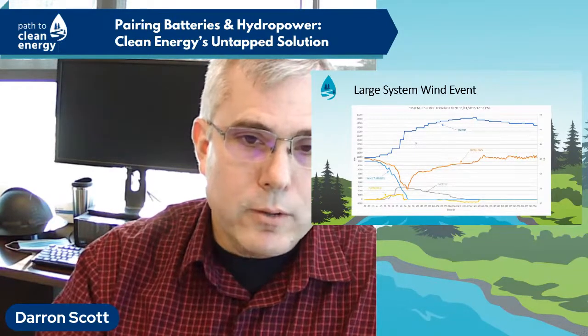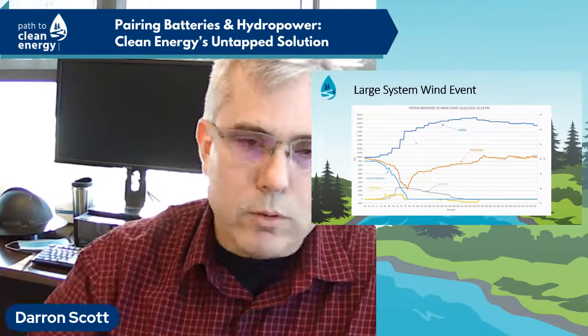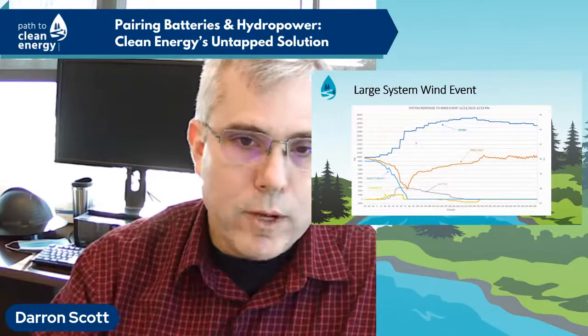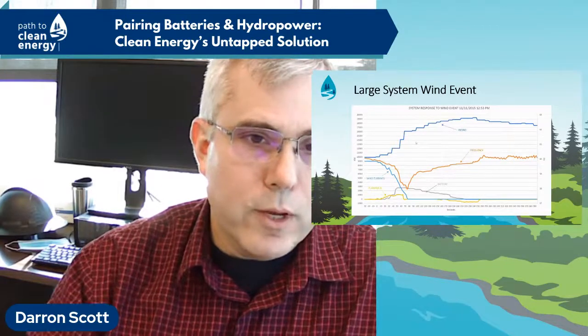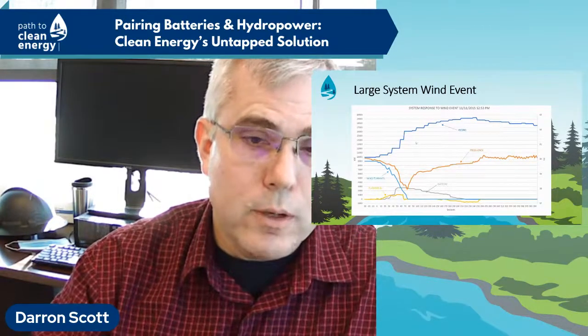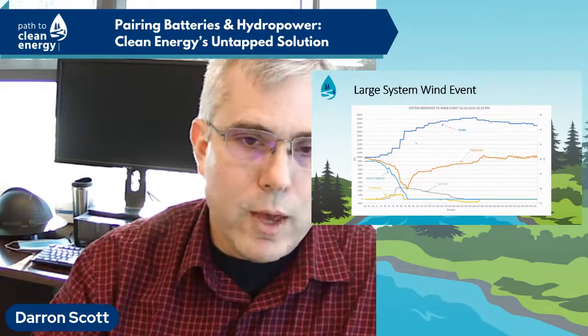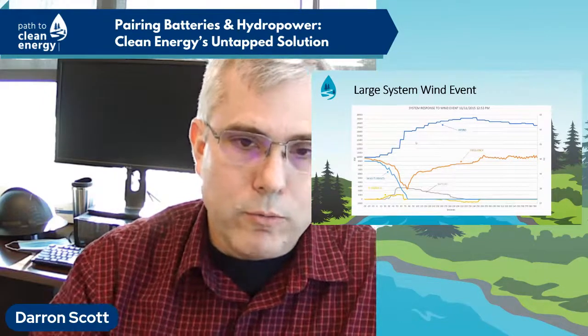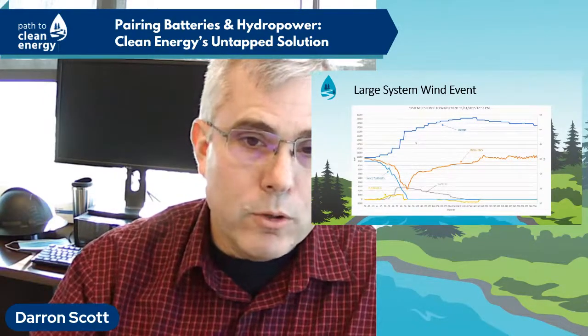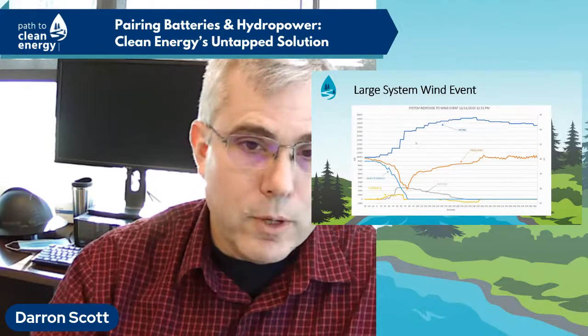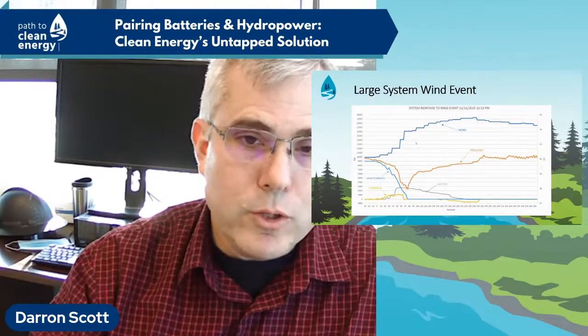That's why they're not 3 megawatts for an hour or two of energy storage. We've got them tuned down to 3 megawatts for 15 minutes, and that might even be a little rich, but it's there for some other issues on our system that are a little different than this. Primarily what we use them for is just a few minutes of power given a situation like this.